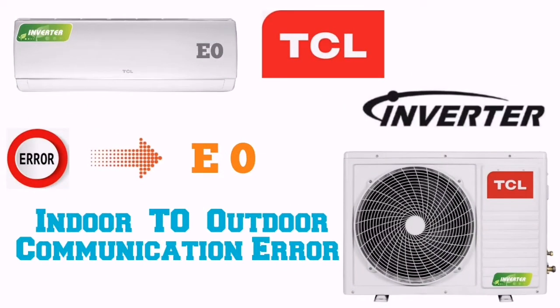When we see error E0 in our indoor unit, it means indoor to outdoor communication error. First of all, we have to check the cable and the connection of indoor and outdoor, to see if they are connected properly. If they are connected properly, then we follow the next step. Then we have to check whether the terminals of indoor and outdoor are good or not. If they are good, then we go to the next step again.